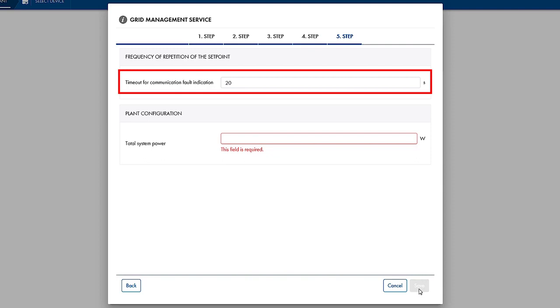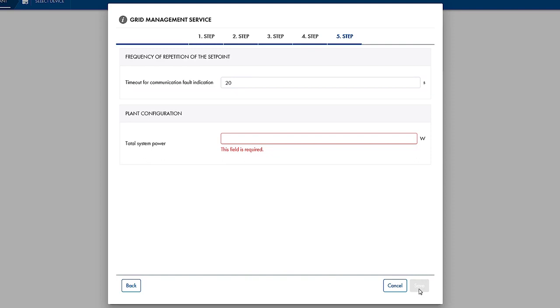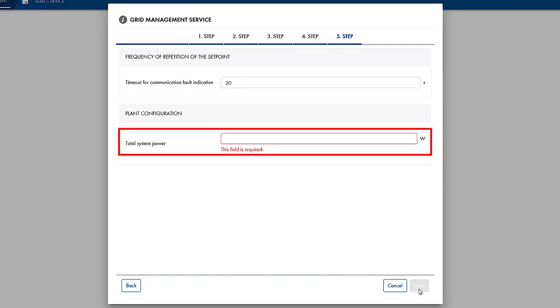If the setpoint does not change, the same value will be repeated after the specified time, here 20 seconds. This ensures that the fallback process, loss of communication due to a missing setpoint, for the inverters is not triggered.